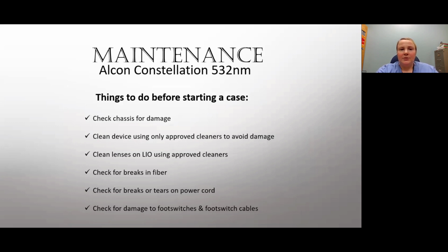So some things to do before starting a case. Check your chassis for damage. Just look around the machine, make sure there's no cracks, no damage on the cord, power cords, the screen. Make sure your touch screen's working. Also clean your device using only approved cleaners to avoid damage.